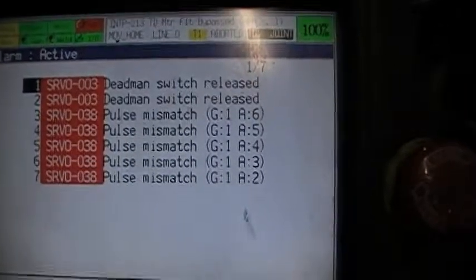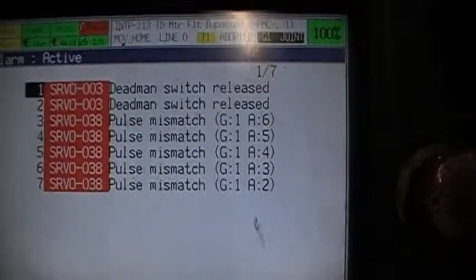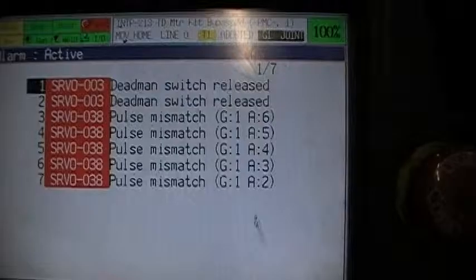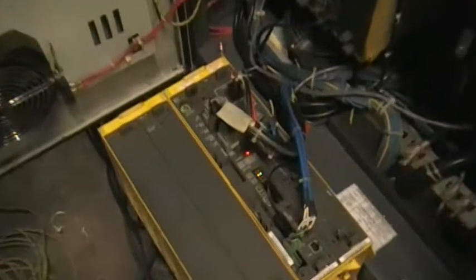Okay, we do have a deadman switch released and a pulse mismatch. This is actually a normal alarm because my original controllers got encoder values for the motor. The encoder positions are different than in my control, the original one and the one we are testing right now.